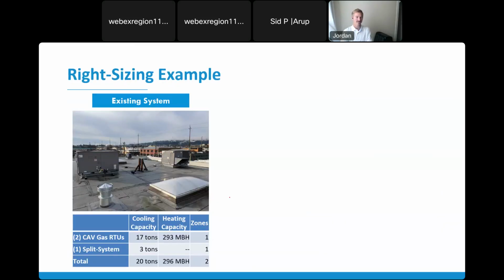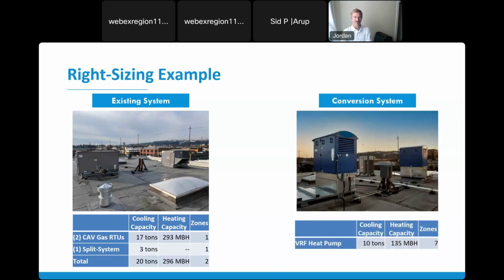Yeah, just more on the sizing. Here are the 2 packaged gas rooftop units replaced with 2,000 CFM ventilators on roof conversion curbs. So we were able to utilize the existing curbs with just curb adapters. Very straightforward. We used a local contractor that did a great job, but just somebody who does rooftop conversions all day had no problem with this installation. Very straightforward conversion from constant volume packaged units to this very high efficiency DOAS concept. But again, 20 tons down to 10 tons, so we cut the system capacity in half.